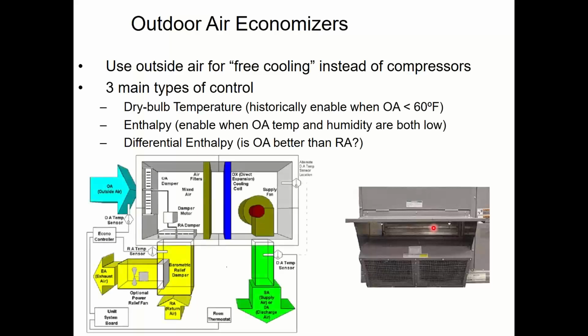So in order to control this, I need a system to do this, not just a damper actuator to modulate this damper, but I also need something to control the system. In other words, decide, is it nice outside? For Thanksgiving, you knew it was. You're hot inside. You already know that it's cold outside. Just go ahead and open up the window. Open it up. Just do it, right? Well, if I'm going to automate this, I have to define what nice outside means, what cool outside means. So there are 3 ways we can do that for most building types, at least here in the Northeast and in the Midwest. The main normal way to do it is what's called a dry bulb economizer.